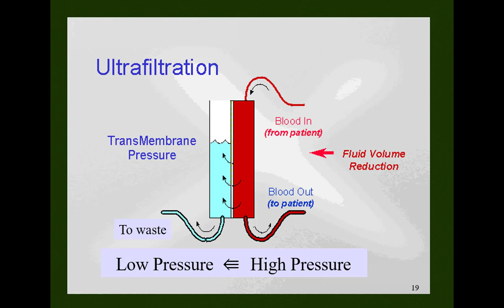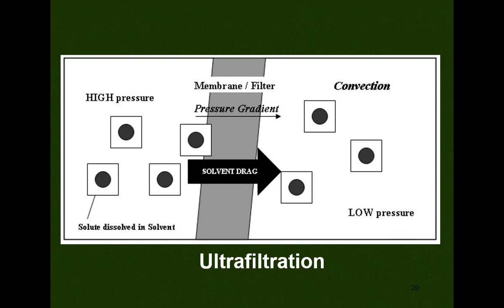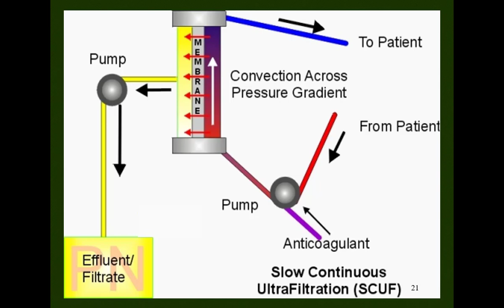Of course, what would be a determining factor here? One is the pressure gradient, and obviously the size of the pores, which will determine how your solute comes out, and this method is called convection. So ultrafiltration is across the membrane pressure gradient, and the method is convection. This is a ray diagram of renal replacement therapy showing ultrafiltration: from the patient, the pump goes to the membrane and returns back to the patient, and this pump creates a negative pressure. So there is a pressure gradient. This pump is responsible for the ultrafiltration, and whatever comes out is called the effluent. It is purely equal to ultrafiltration.